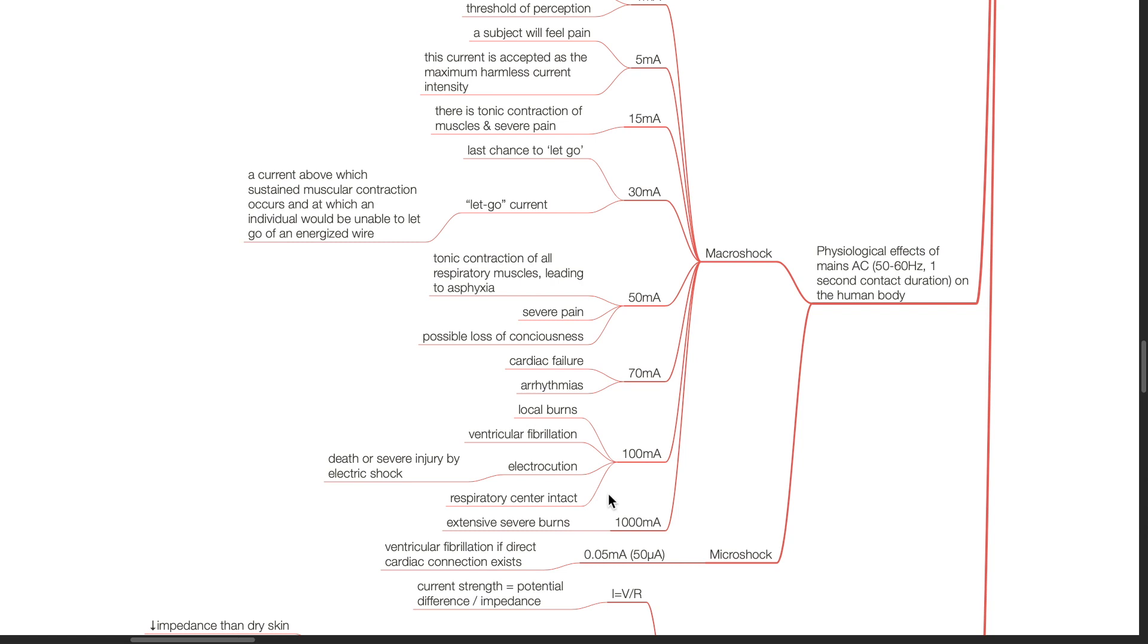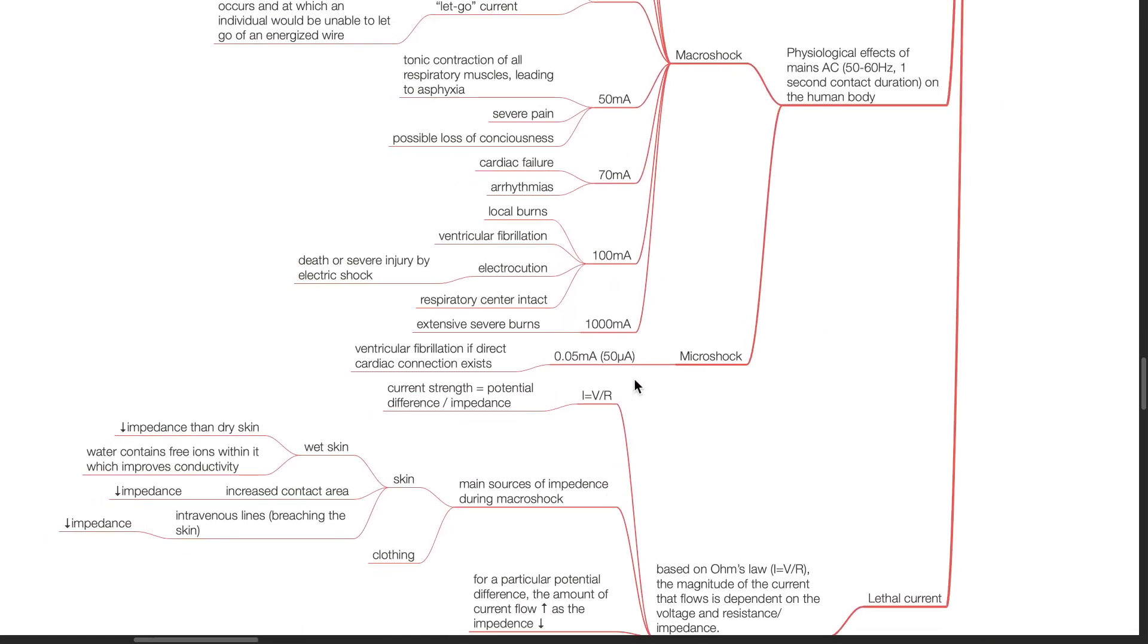At 1000 mA, extensive severe burns occur. Microshock occurs at 0.05 mA. Ventricular fibrillation will occur if direct cardiac connection exists.